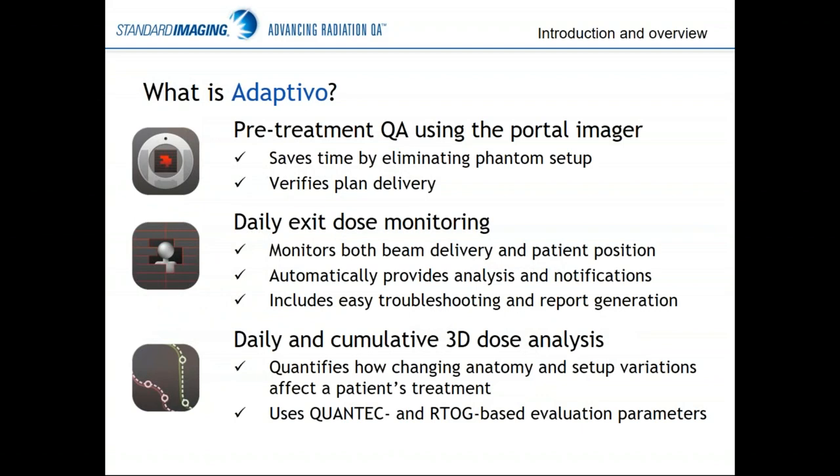So what is Adaptivo? It is three things. The first is pre-treatment QA, just using your portal imager. So if you're still using a phantom like a MapCheck, ArcCheck, or Delta IV, you can save a lot of setup time by eliminating this phantom from your workflow. You can verify your plan delivery just with a through-air delivery to your portal imager.